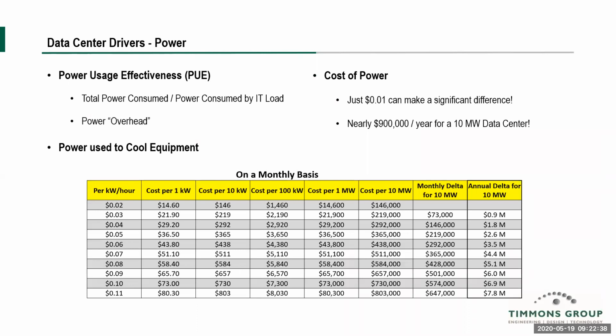One important metric when measuring the power success of a data center is power usage effectiveness. This is computed by the total power consumed divided by the power consumed by IT load. This is essentially calculating your power overhead, much of which is made up of the power utilized to cool the equipment.